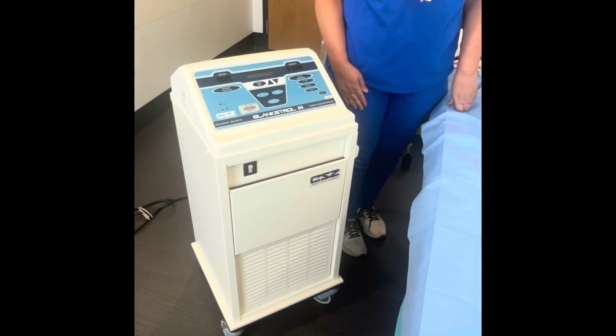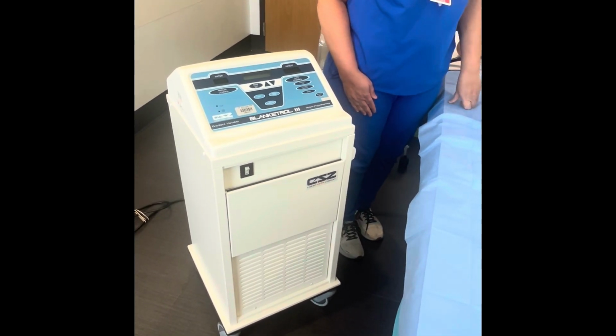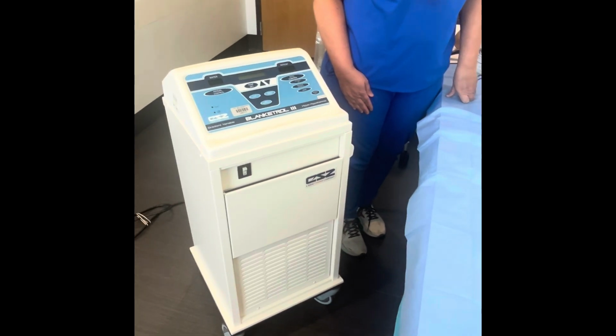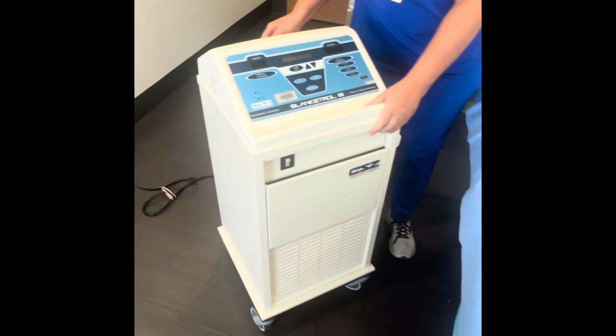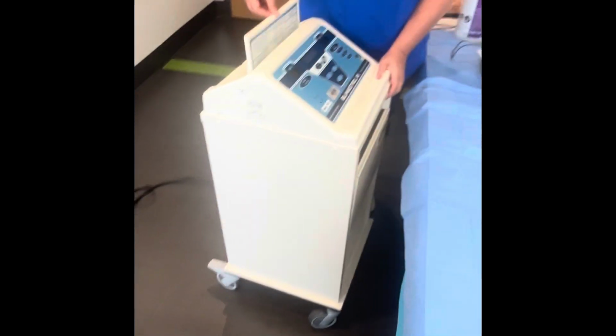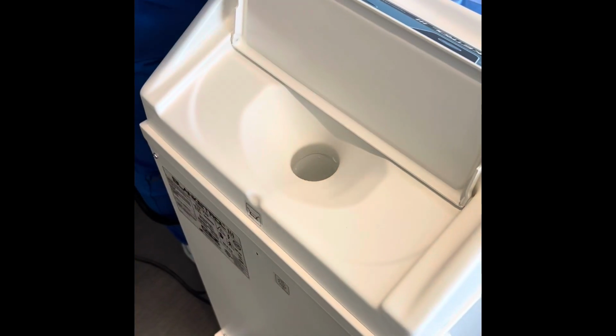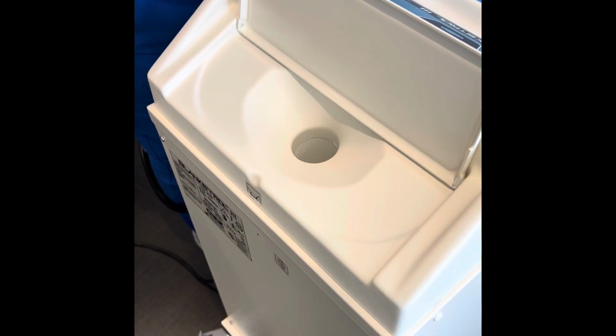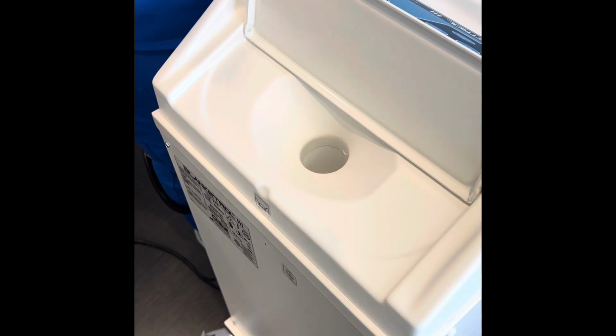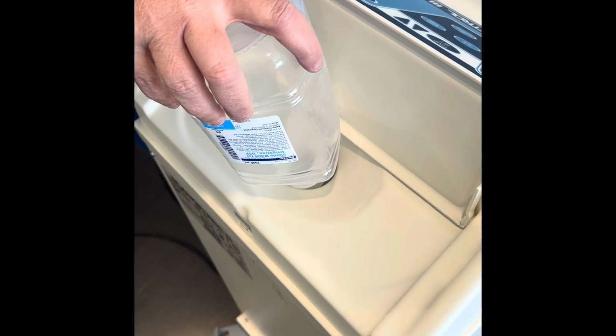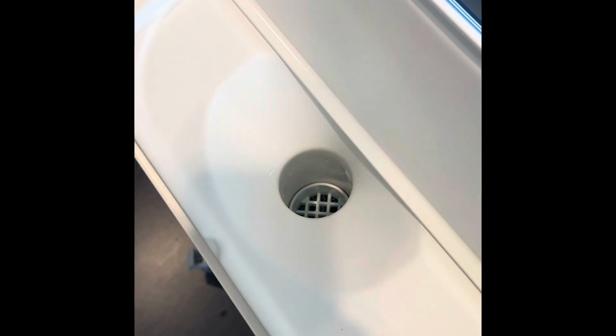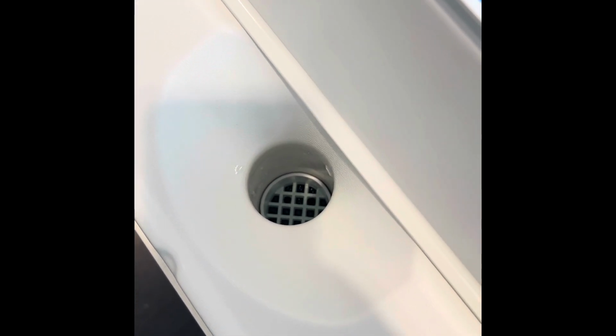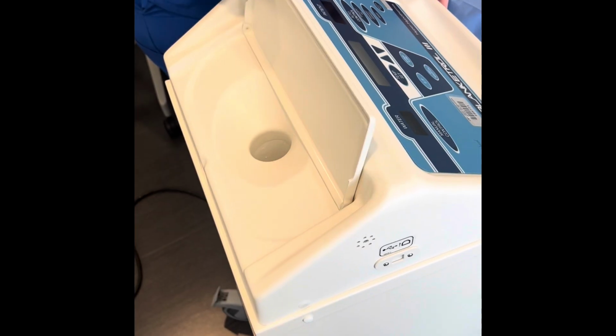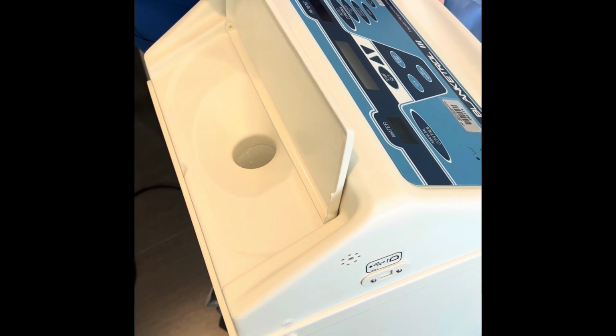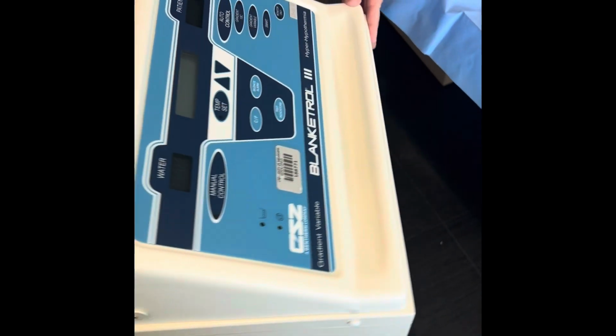Turn the radiant warmer off during your course of hypothermia treatment. Lift the cover of the water fill opening on the back of the cooling blanket machine. Check to determine if water needs to be added. To add water, fill the reservoir with sterile water to the designated level. Water is visibly touching the strainer. Close the water fill opening on the back of the machine.